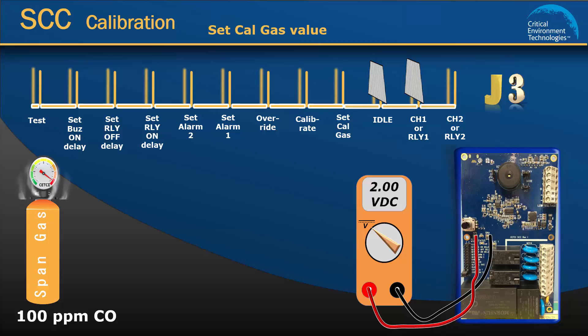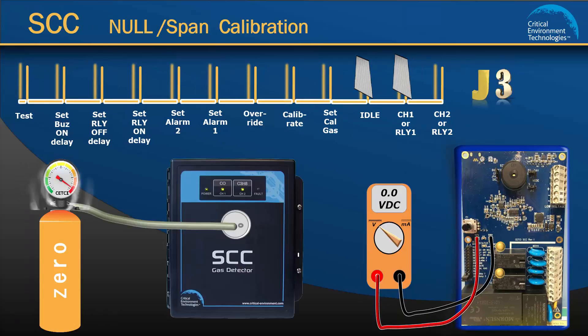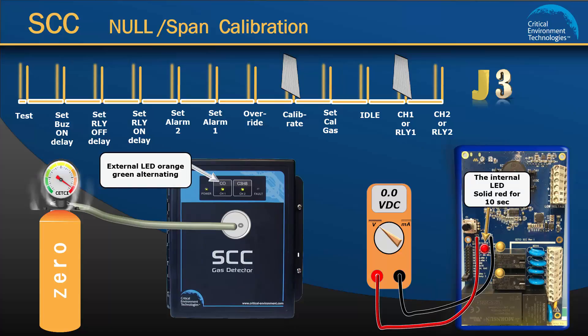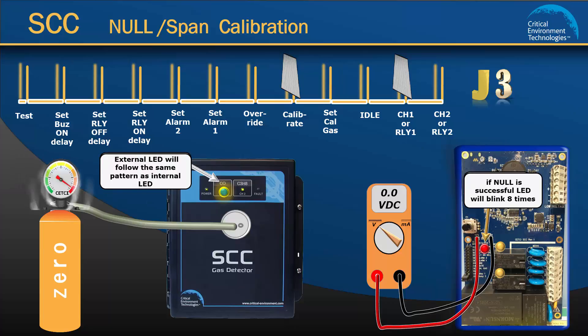To begin the null calibration, attach the regulator to the cylinder, insert the calibration adapter into the sensor opening in the front of the enclosure door, and open the regulator valve fully allowing the zero gas to flow over the sensor. Move the jumper from the idle position to the calibrate position. The internal LED will be solid red and stay on for 10 seconds. The external channel 1 LED light will alternate orange and green. The voltmeter should read zero. If the null calibration is successful, the internal LED and external channel 1 LED lights will blink 8 times.